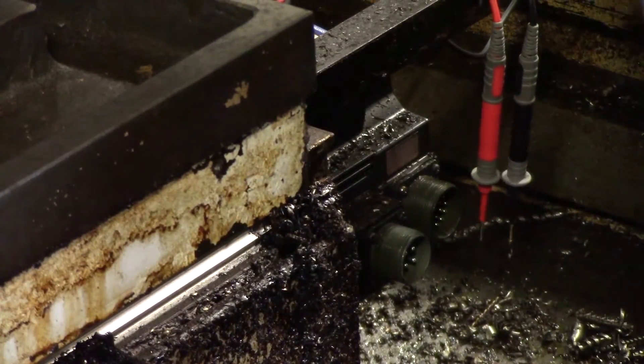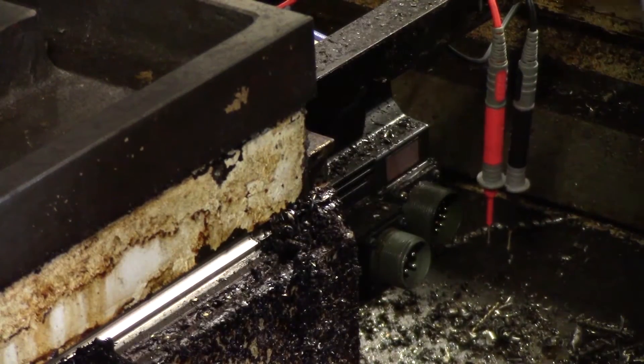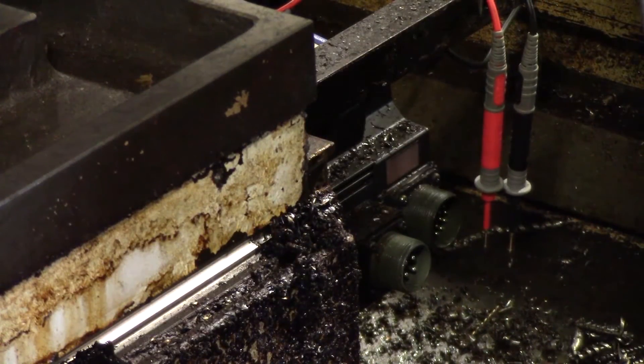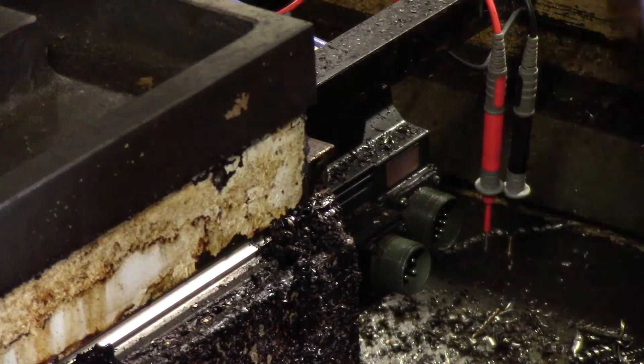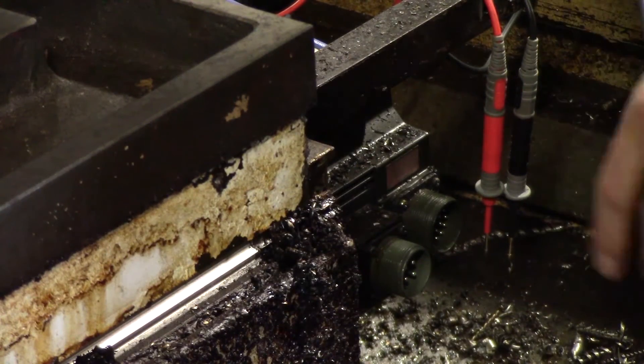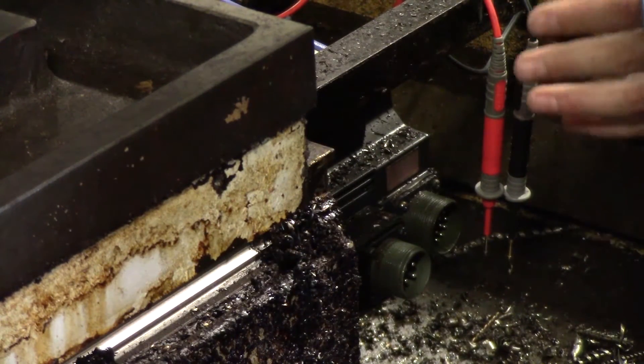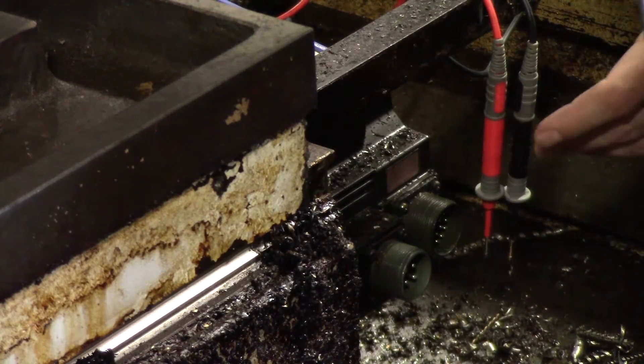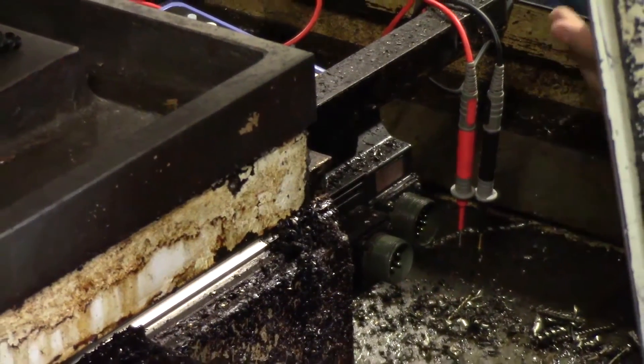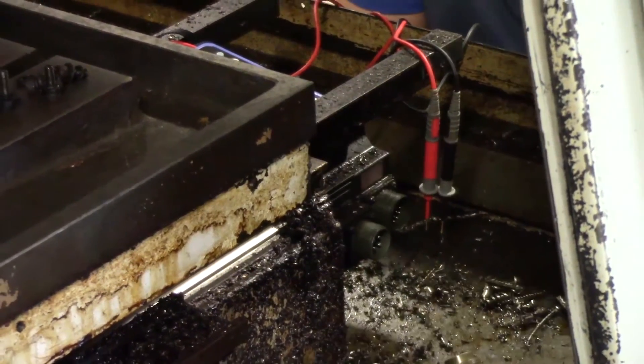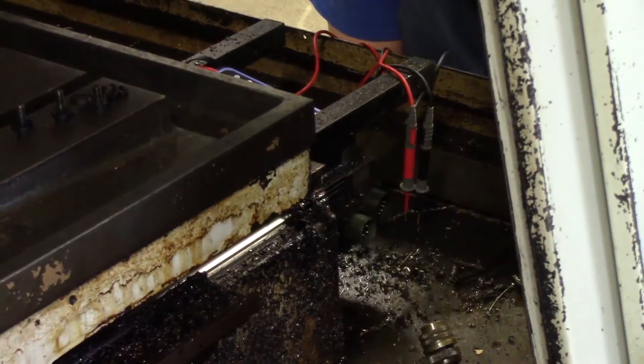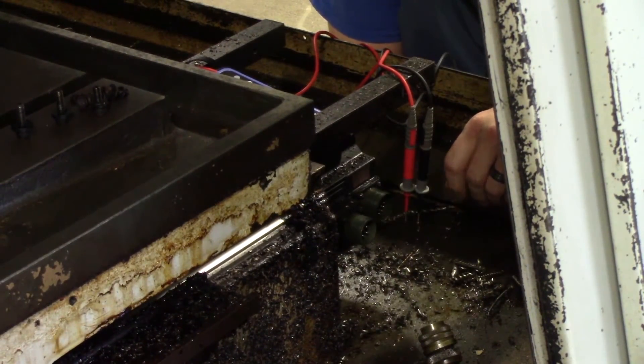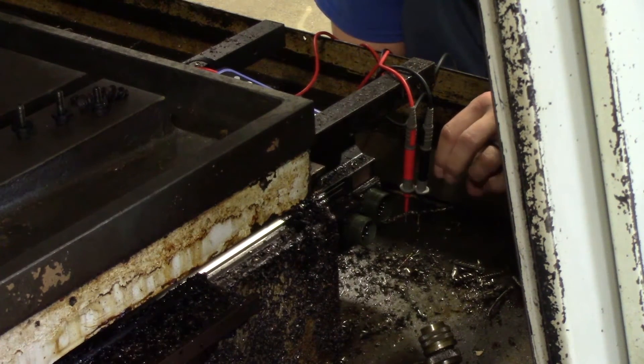So at this point if we were chasing a problem you should have found a problem with the motor which wouldn't have been a super surprise considering how dirty this thing is, and then at that point you would want to pull the motor and send it in for repair. Remember we recommend anything under 300 mega ohms a cause to send it in and have it properly evaluated.